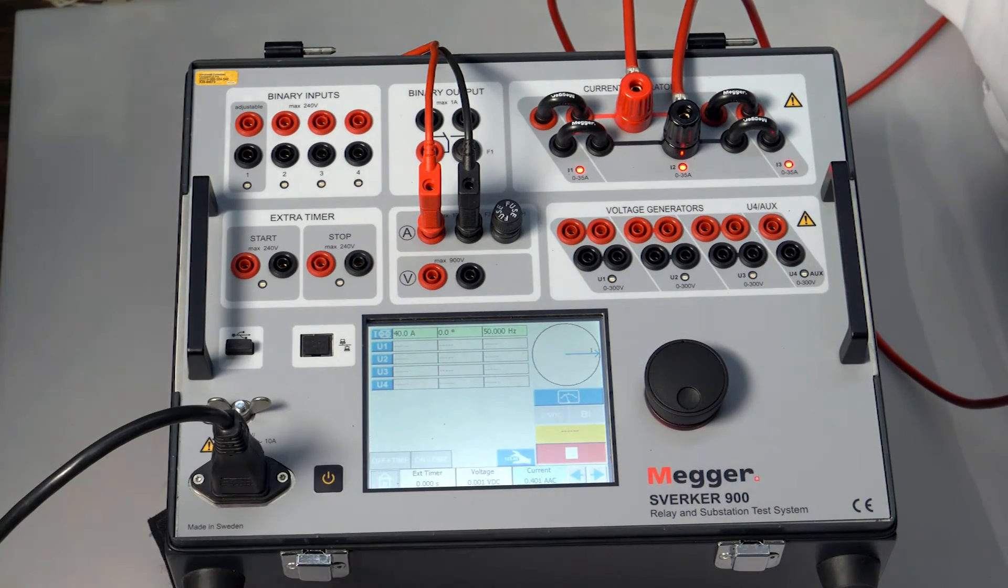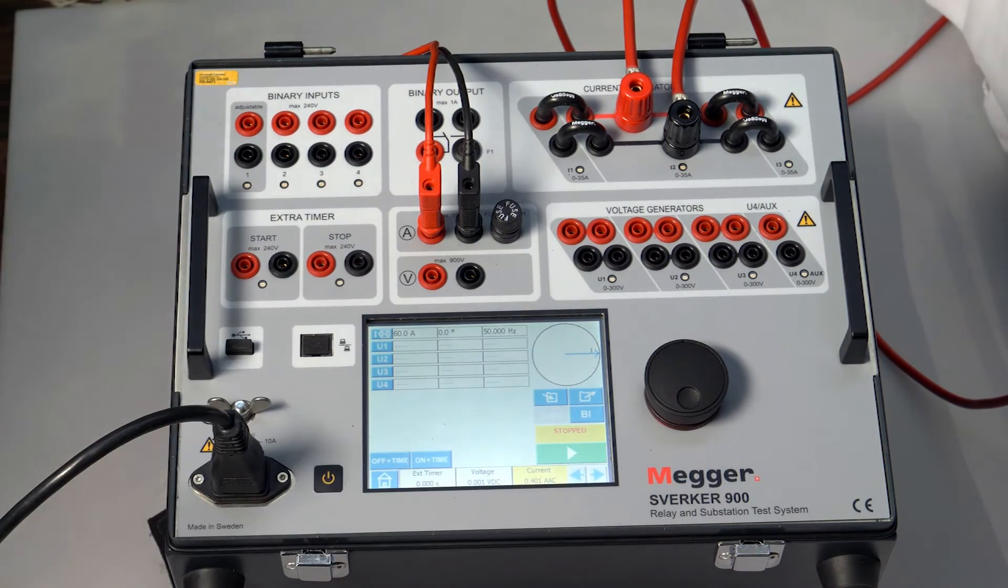Let me repeat for 40 amps. Theory value is 0.4. The reading is 0.401. 60 amps theoretical calculation is 0.6. The measured value is 0.602 amps.